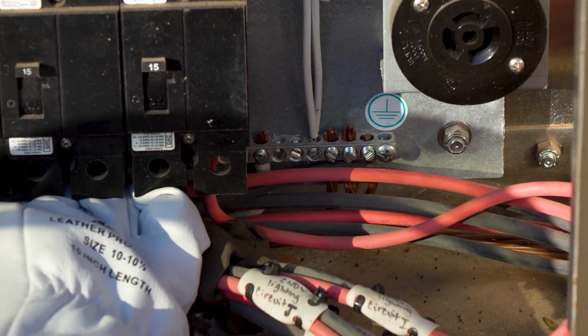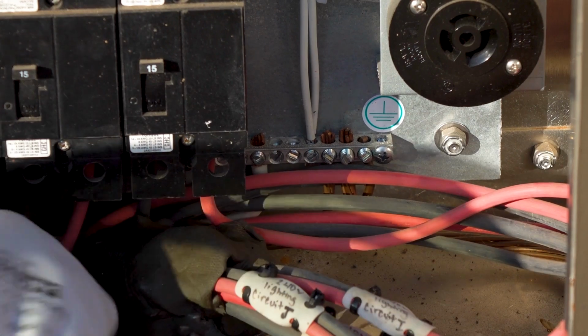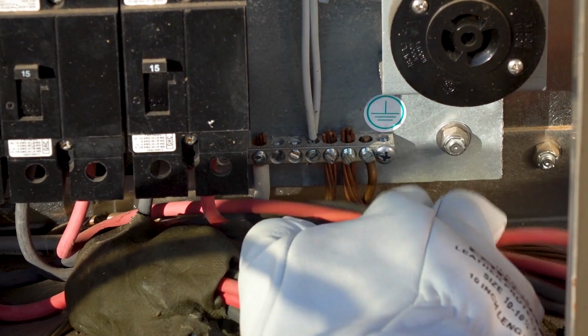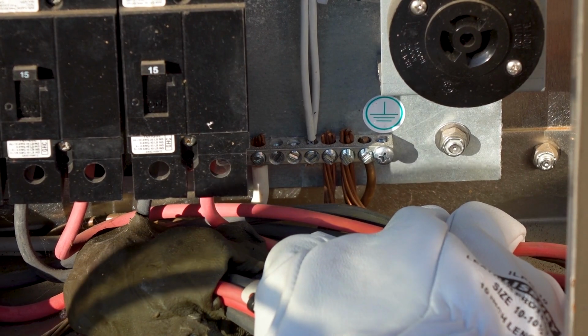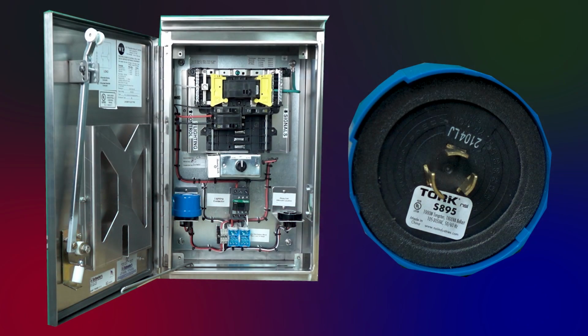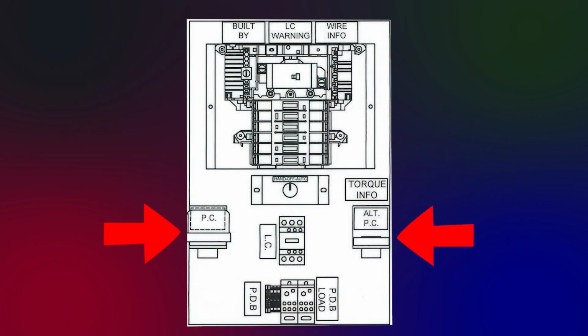The blocks are noted on the panel layout diagram and should also be marked within the panel. The inspector should visually confirm that each conductor is held tightly under its screw and that none of the conductor strands have been cut off or damaged. A light-sensitive photocell switch is used to turn the lights on at dusk and off at dawn. The photocell can be located either on the service support structure or within the enclosure itself. The inspector will need to review the descriptive code for the service being inspected to determine the photocell's specified location.